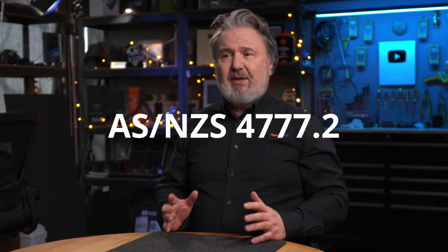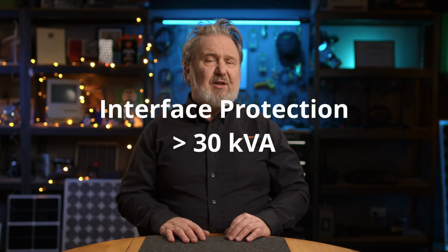First up, IPSDs can only be utilised with inverters that have been tested to ASNZS 4777 Part 2. That's the inverter test standard. The IPSD shall have interface protection if the IES is over 30 kVA. So that's interesting. The 200 kVA limit for without requiring interface protection applies for all other systems except for IPSDs. You're back down to 30 kVA without interface protection. It's a requirement that if any one of the distribution boards supplied by the IPSD, so one of those apartments, loses grid connection, then the IPSD must island within 2 seconds. So it must fulfill the anti-islanding function. Therefore, effectively, all the apartments would lose their supplementary supply. They'll still have power, if they did have power, from the grid, but they will lose their solar contribution.